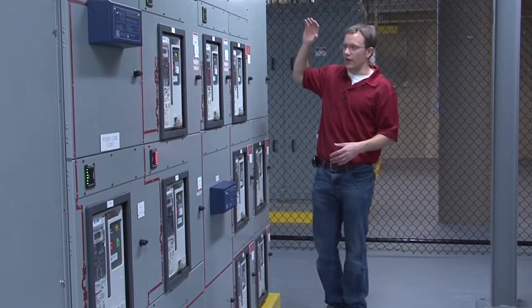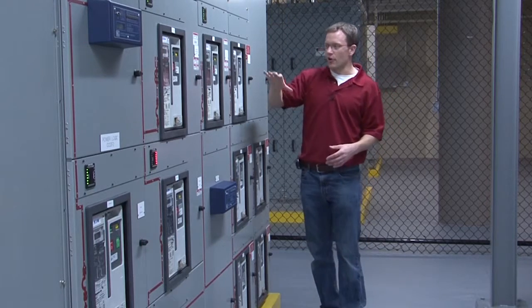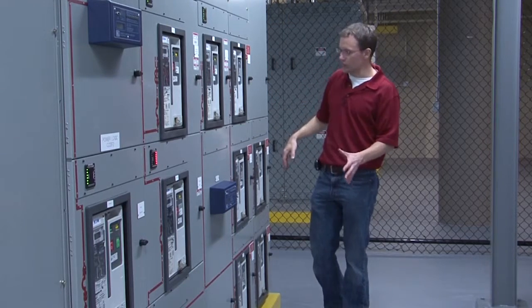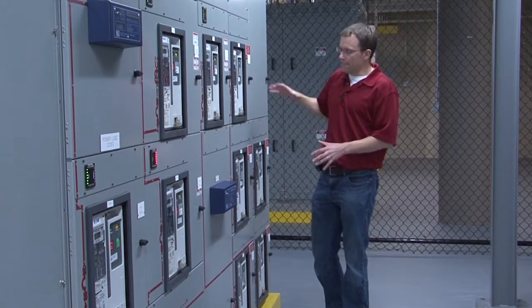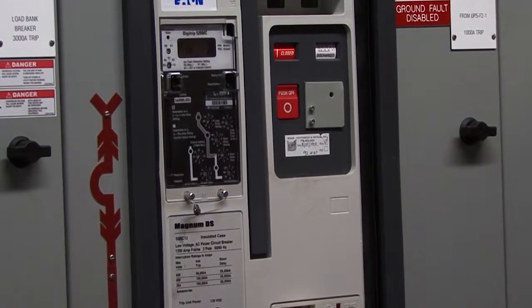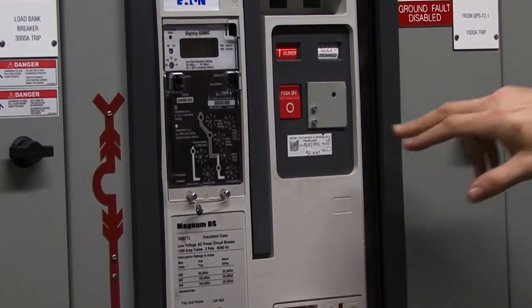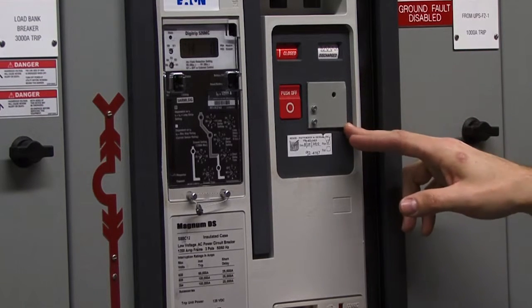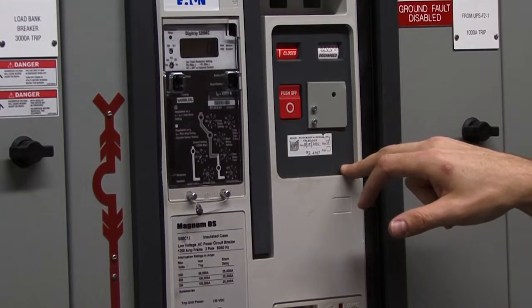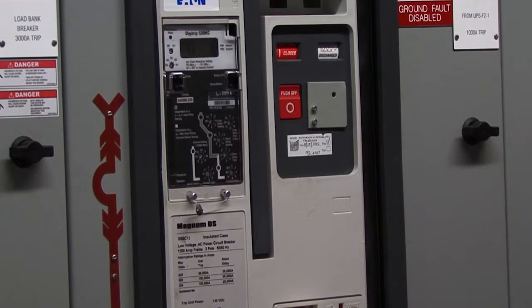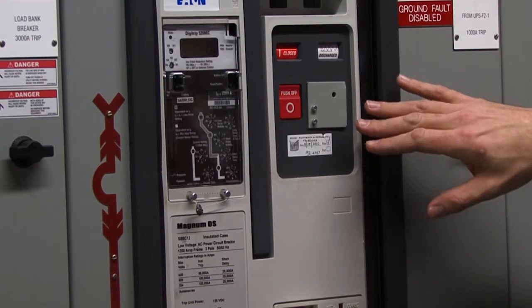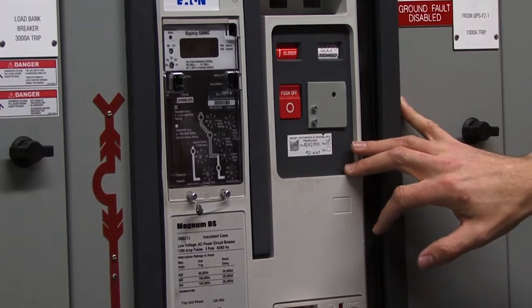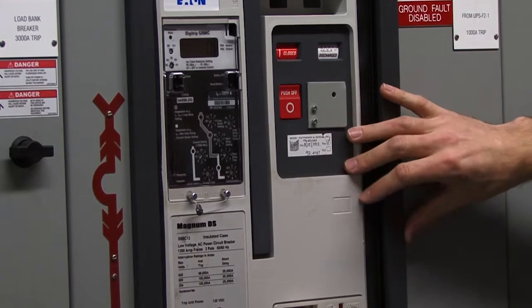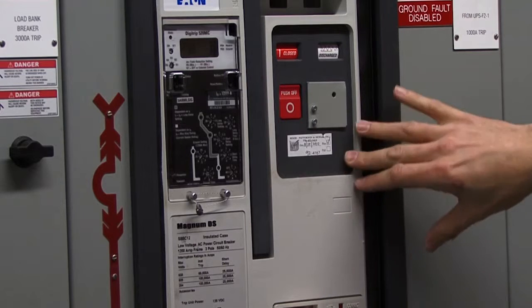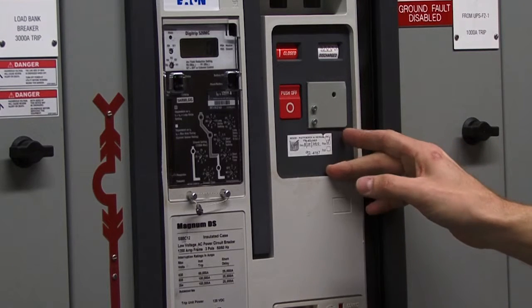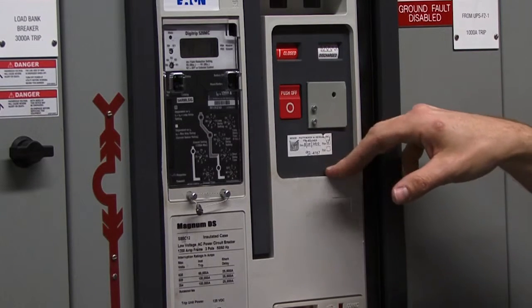Similar to the breakers down there, these breakers are all monitored by Convergent. But the input breakers do not have closed button cover plates because it's never unsafe to close those breakers manually. That's not really the case on the output. On these output boards, which are called MOBs, module output breakers, if you close them when you shouldn't, you can cause instability in the UPS system.